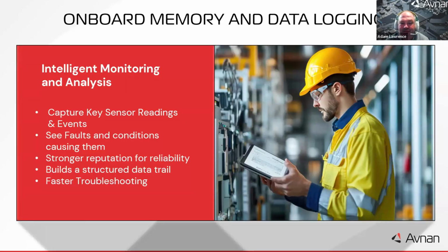Another key part of the architecture is onboard memory with integrated data logging. By capturing key sensor readings and events, the controller builds a structured data trail that supports your diagnostic strategy. This built-in logging allows technicians and engineers to instantly see faults and the conditions that caused them, without external data loggers or recreating conditions, allowing faster troubleshooting, less downtime, and higher reliability. Beyond simply recording data, the log's standardized structure makes it easy to interpret and align seamlessly with the diagnostics framework built into every unit, shifting from basic control to intelligent monitoring and analysis.